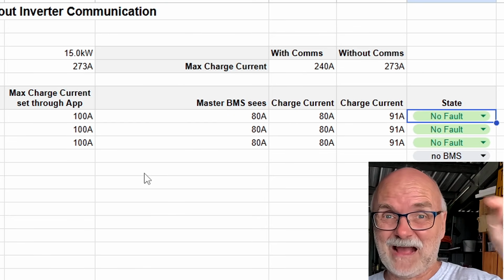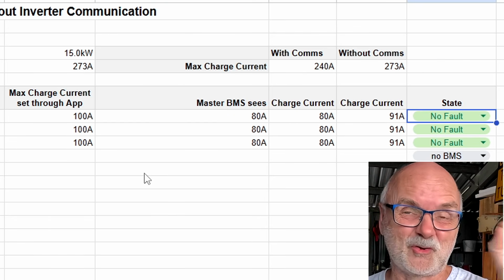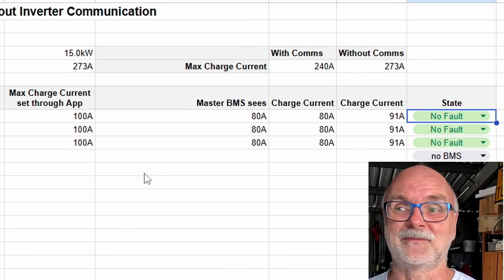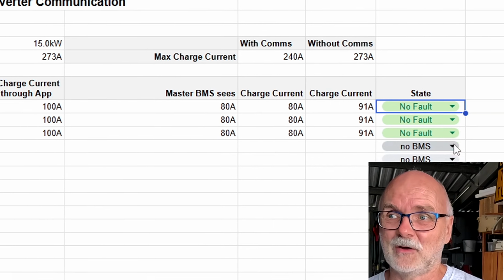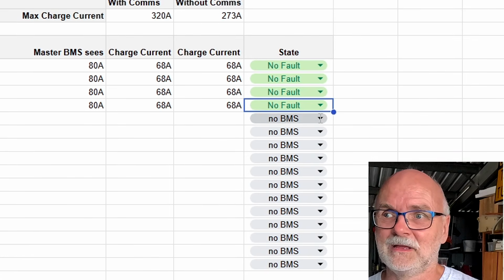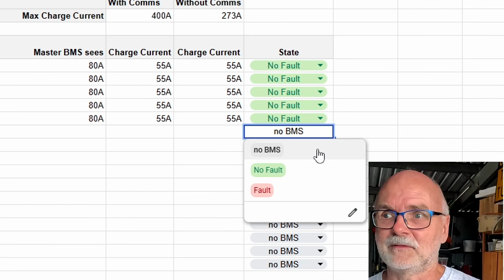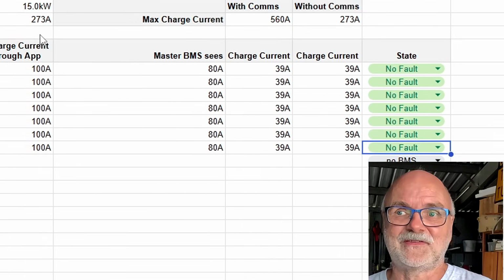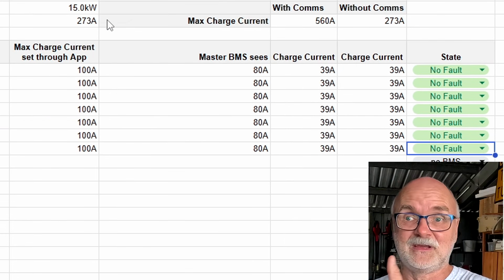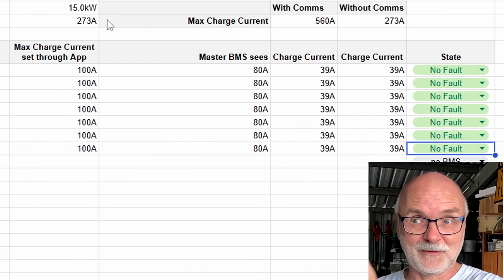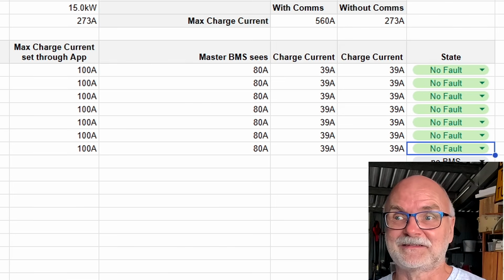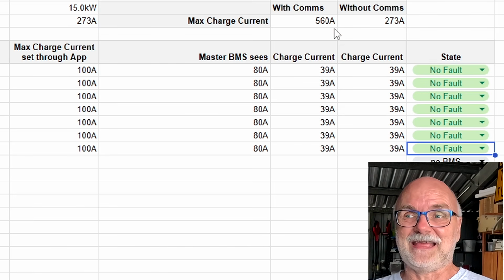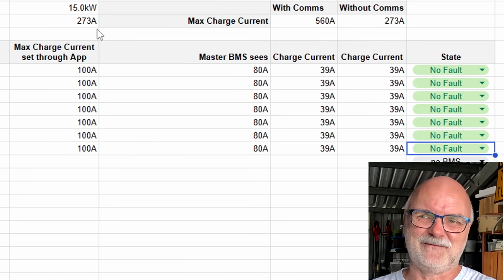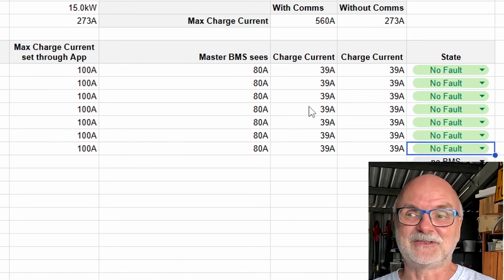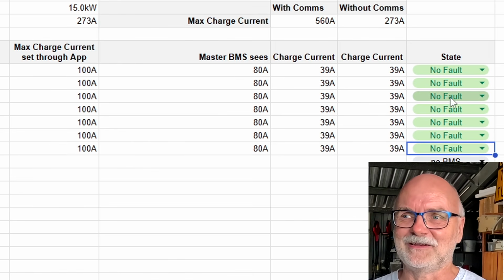So now back to this argument of some saying communication is only necessary if you have larger systems, more advanced systems or something. What about if we introduce more batteries here? Let's say we have 7 batteries now connected, with the same 15 kilowatt solar system I have here. Not uncommon for me to have 7 or even more batteries connected. We're requesting 560 amps now from the inverter. It can deliver only 270, so it doesn't really matter. We are charging each battery with 40 amps max, totally fine, totally safe.